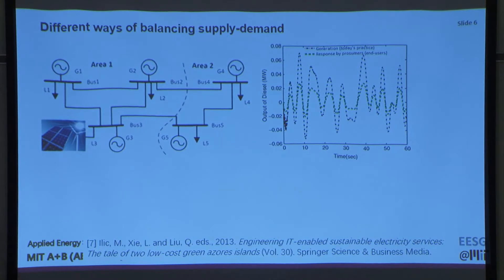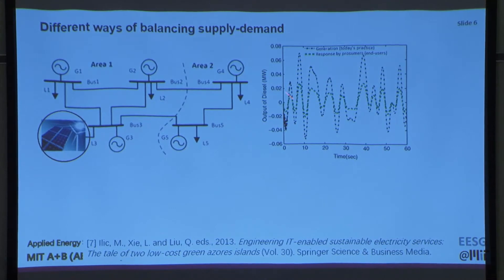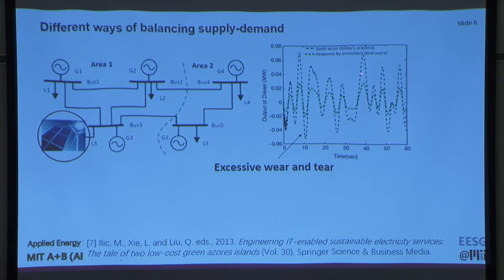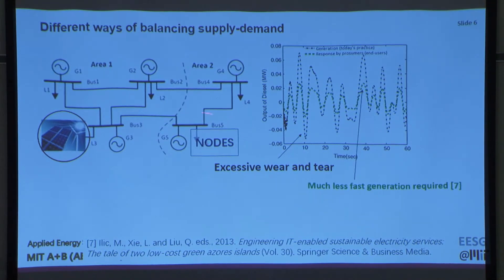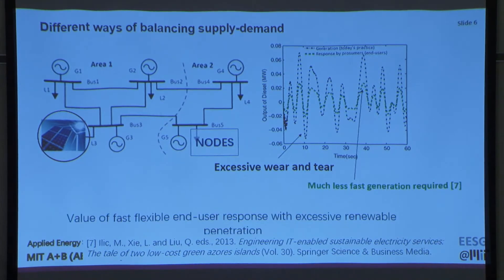In this plot, the high voltage part of the grid has a lot of solar penetration, which shows up as an increased requirement to chase fast supply-demand imbalance. Today this is handled by automatic generation control (AGC), resulting in increased wear and tear on generators ramping up and down at very fast rates. But if we make use of an aggregate of demand-side resources through the NODES framework, it is possible to cut down on the fast, expensive generation needed, shown in green here. This captures the value of fast, flexible end-user response.